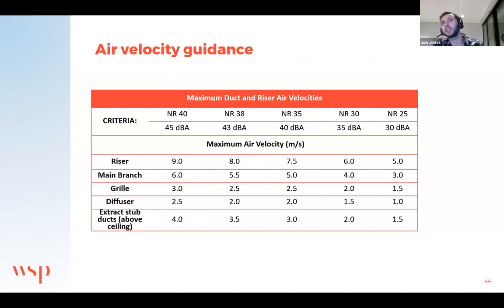Table here just to summarize again, when we know what systems we're looking at, we can advise as acoustic consultants on maximum recommended air velocities. The table here we're looking at is the acoustic criteria per column for, say, typical 30, 35, 40, 43, 45 dBA acoustic criteria. That translates into maximum advisable flow rates for different areas of ventilation systems. So that's something we can look at and consider and advise on in a design.